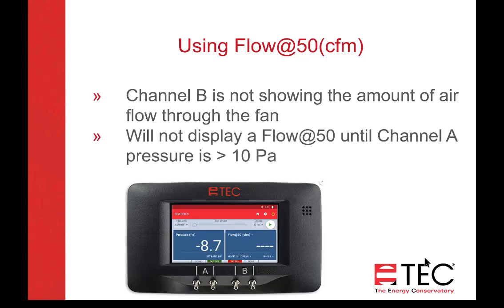And it won't display a flow until the pressure on channel A is above 10 pascals. For the blower door, it needs to be above 10. For the duct blaster, it needs to be above 5 pascals. If you ever see four dash lines on the gauge, that means you're in a flow at 50 mode, and the pressure isn't high enough on channel A for it to do a conversion between the flow through the fan and what the flow would be at 50.